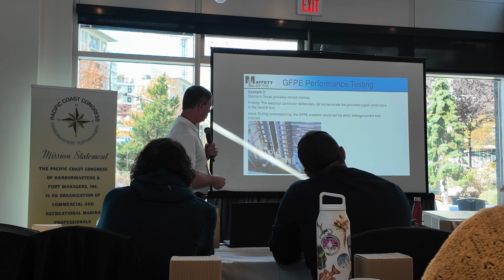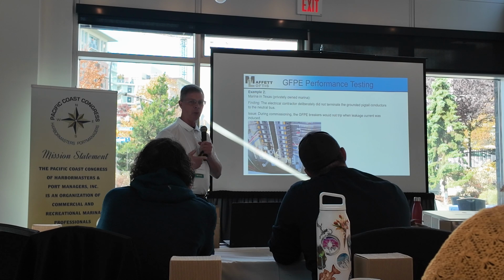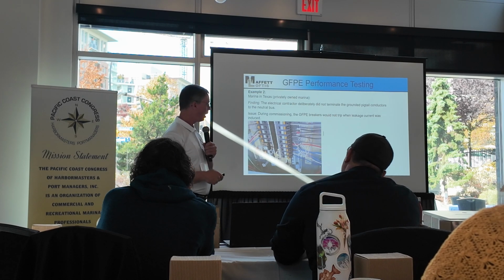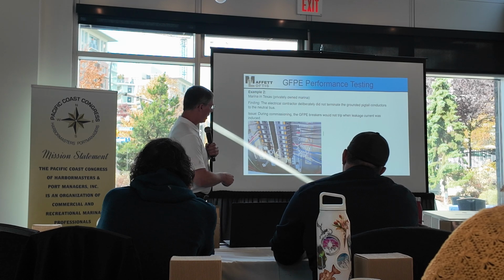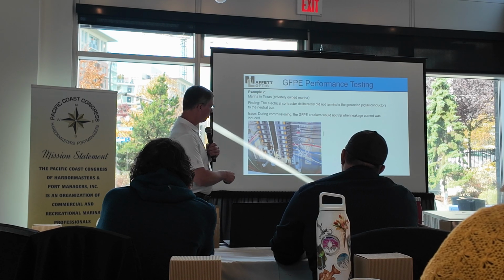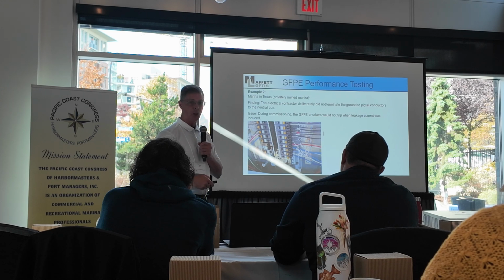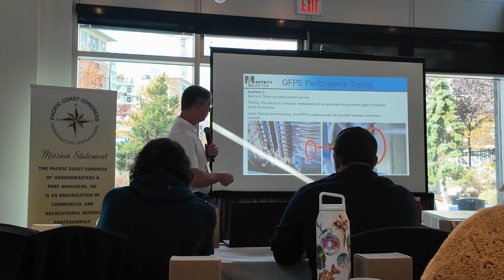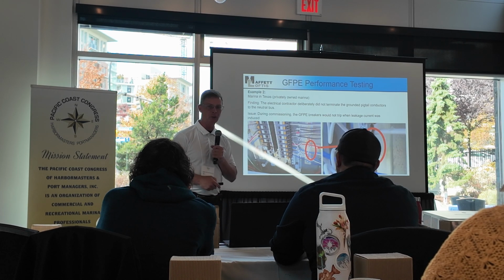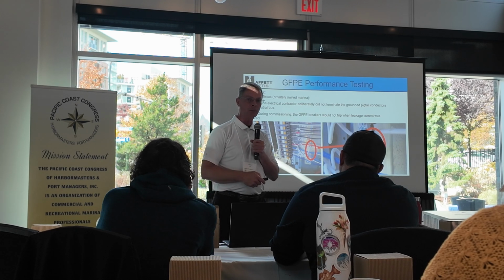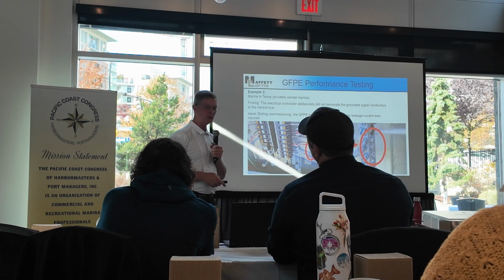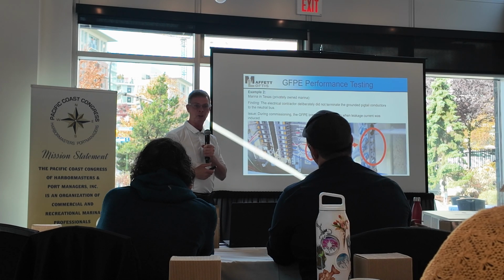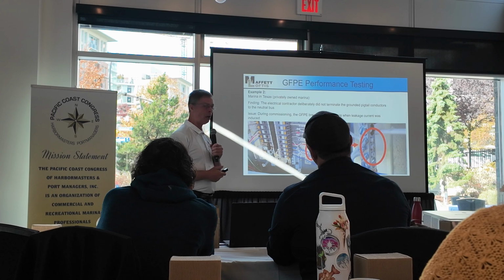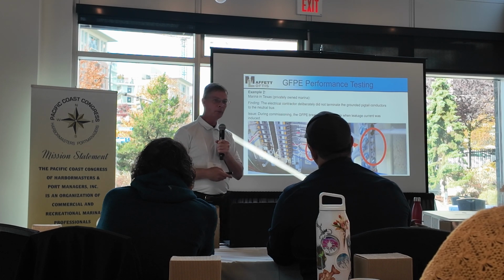Here was a project out in Texas, and they did not wire the system like I designed it. They used common neutrals through multi-branch circuits, and they could not get the GFPE breakers to work. So instead of bonding their neutrals to the bus, like they should, and like code, UL and the manufacturer require, this is what they did. They cut the copper off and left the insulation on to make sure that the power would stay on. The inspector didn't see this because it wouldn't be something you'd normally look at, and it made it look like those neutrals were actually bonded to the bus, but they weren't.